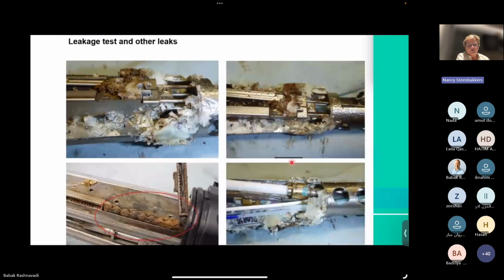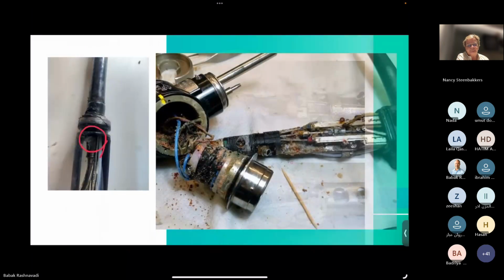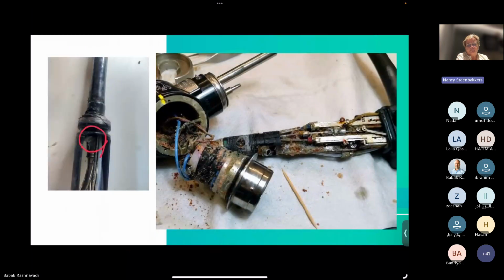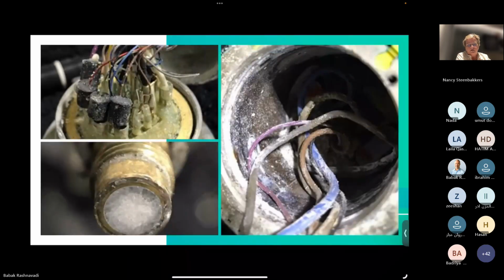So you have to perform your leak test in a dry way for 2 minutes before you soak it underwater, and then you will not have this kind of situations. So you really can avoid all kind of repair costs if you do it in the right way. Next, please. Here is another example: because of not doing the leak test in a good way, you are creating all kind of damages in your endoscope. Next, please. This is another one. Next, please.